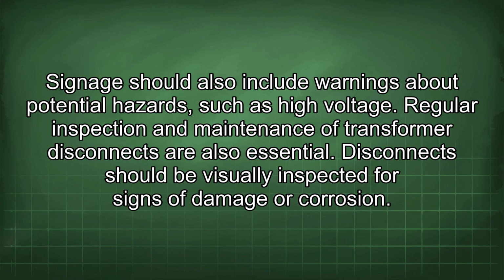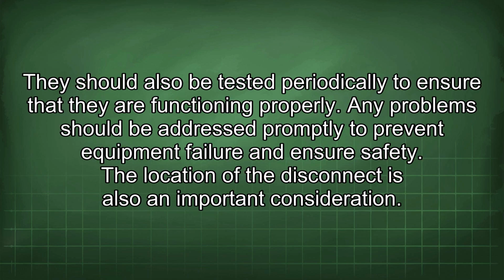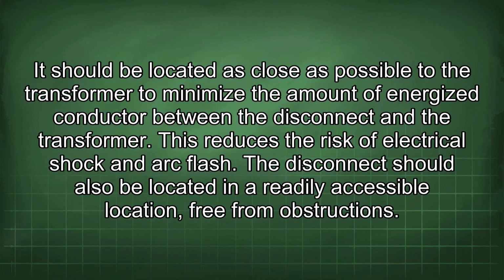Regular inspection and maintenance of transformer disconnects are also essential. Disconnects should be visually inspected for signs of damage or corrosion. They should also be tested periodically to ensure that they are functioning properly. Any problems should be addressed promptly to prevent equipment failure and ensure safety. The location of the disconnect is also an important consideration. It should be located as close as possible to the transformer to minimize the amount of energized conductor between the disconnect and the transformer. This reduces the risk of electrical shock and arc flash.